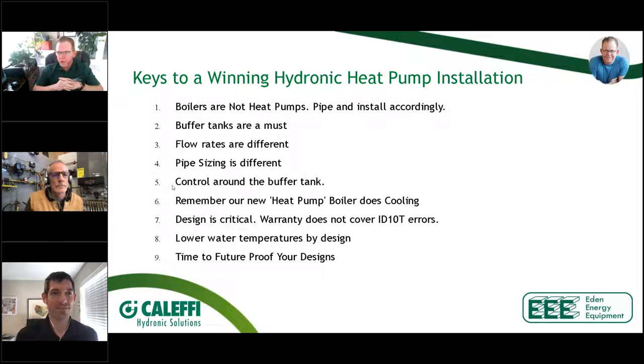The other thing that's important to touch on is buffer tanks. Bob's going to talk about this in one of the slides, but buffer tanks on heat pumps are a must. There are a few manufacturers out there that don't need buffer tanks on their air to waters. We had a conversation before this webinar started where we've got a lot of questions. Good news is these manufacturers want our feedback, so the three of us are going to give them some and we're all going to get a lot smarter for it. But buffer tanks are very critical to heat pumps, and we're going to talk about why in this presentation. Again, flow rates, pipe sizing, all different. Max is going to talk about that, and I'm going to touch on it a little bit.